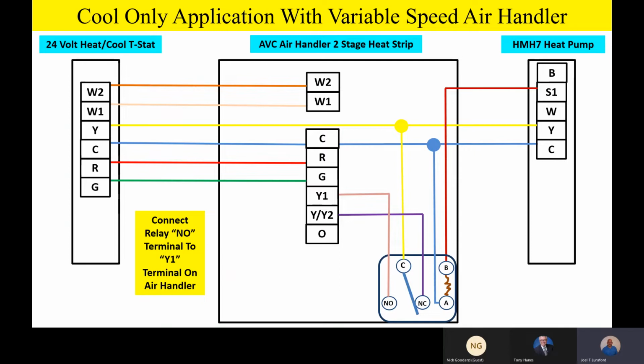But along with that really good question we had a minute ago, what if I'm stuck with 2 wires? If I only have 2 wires outside and I don't use the S1 circuit, what do I do, or what's going to happen? Well, on the variable speed air handler, you can make some tweaks on the airflow adjustments on the control board. We strongly recommend that you set that up at 400 CFM per ton, and then go to the delay jumper and set it for a humid environment, if you're in a humid part of the country. So you can do some things with a variable speed air handler that you cannot do with an AE air handler, as far as tweaking your airflow to give you more comfortable dehumidification.